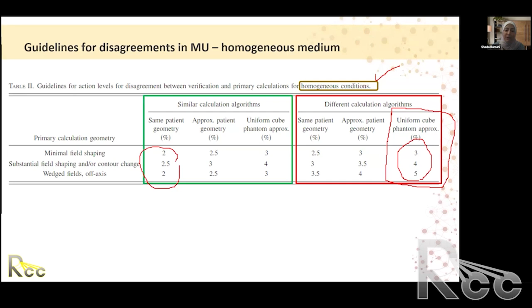Now, 5%, look at this, if we're doing wedge fields off axis. Wedge fields are very complex, but we're only using a single point to account for the wedge factor. The wedge does change the scatter environment in 2D, but we're putting all that in one point. So that's why for wedge fields you should expect up to 5%. If the shaping is minimal, so think of a 4-field box technique where you're blocking just the corner, then I could expect 3% is good enough agreement to say go ahead with treatment. If there is substantial field shaping, like the inverted Y or the hockey stick for Hodgkin's lymphoma and non-Hodgkin's lymphoma, those are very complex treatments, then you should expect around 4%.